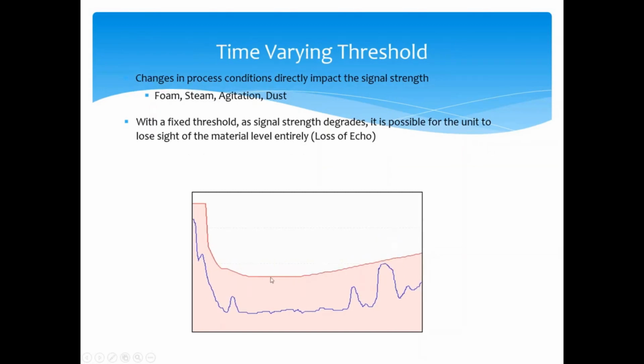This is a static threshold value. In an instrument like this, you would program in, or that instrument would select, a static threshold value that never changes with time. It would only change if you manually go into that instrument and change it. So if you have an application where you do or don't have foam, when the foam's not there you're probably fine with a static threshold. But when that foam shows up and your signal decreases, now you go into echo loss. That's the difference between the two.